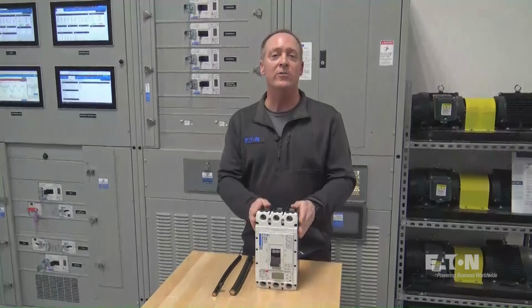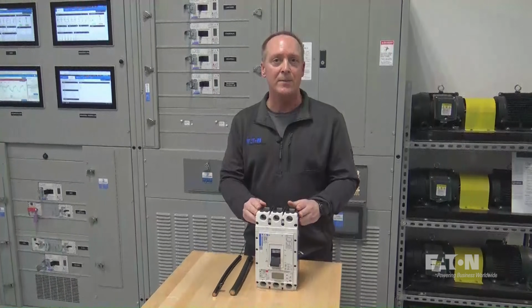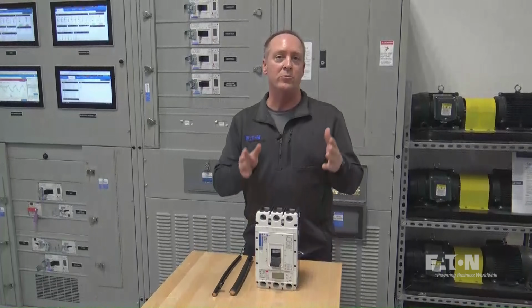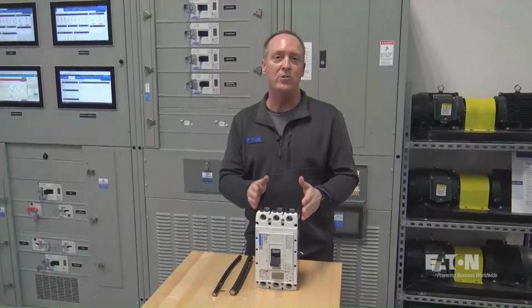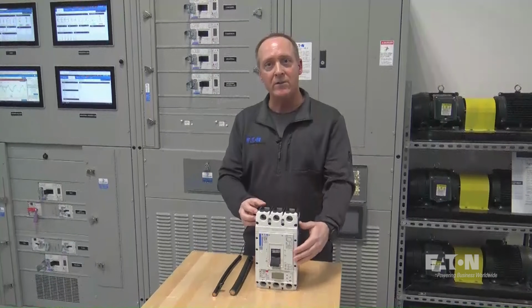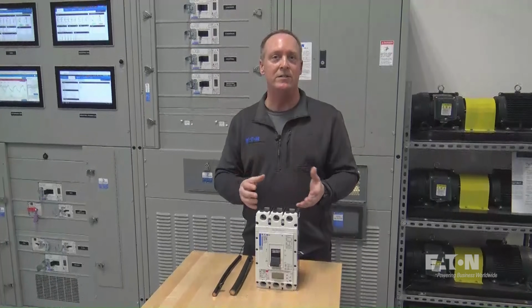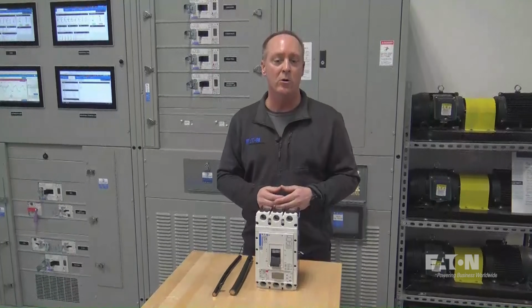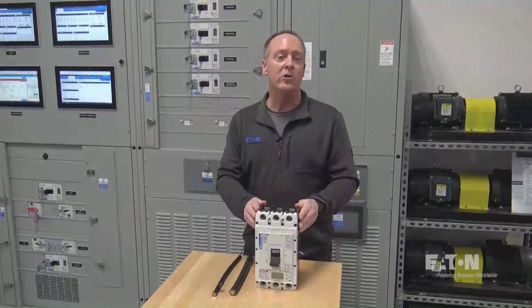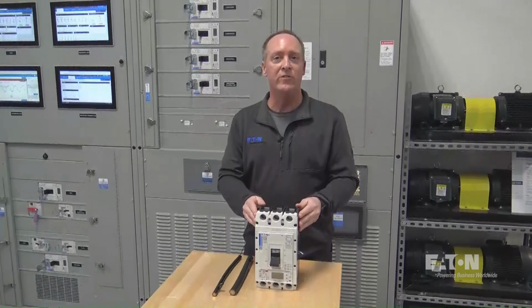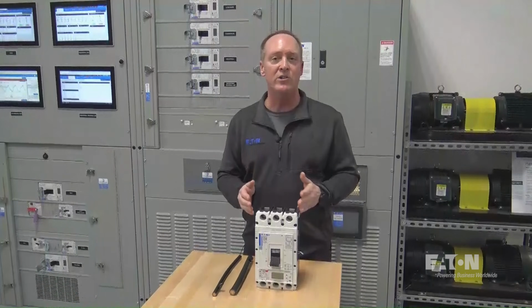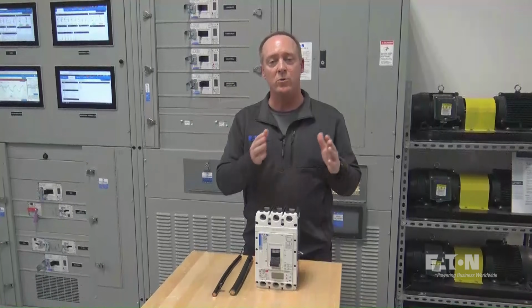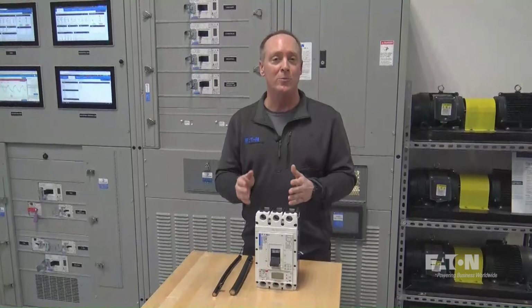The circuit breaker itself is physically the same. The only thing that's different between a standard circuit breaker and a 100% rating, other than the markings, is again the way that it is tested, and tested in a given enclosure. The time current curves are also identical between the two devices.